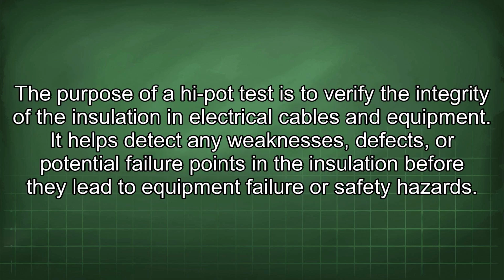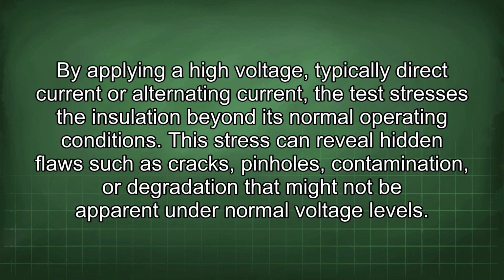The purpose of a high-pot test is to verify the integrity of the insulation in the electrical cables and equipment. It helps detect any weaknesses, defects, or potential failure points in the insulation before they lead to equipment failure or safety hazards. By applying a high voltage, typically direct current or alternating current, the test stresses the insulation beyond its normal operating conditions. This stress can reveal hidden flaws such as cracks, pinholes, contamination, or degradation that might not be apparent under normal voltage levels.